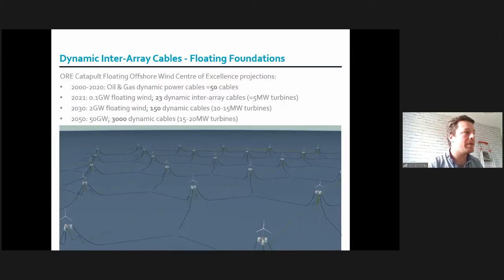So the projections for floating wind that Paul just talked about are very high level. Before floating wind kicked off, we have some quite good experience from oil and gas. So about 20, 30 years of experience on medium voltage and high voltage power cables or umbilicals. And it's maybe about 50 of those cables that we can learn from as an industry and refine those designs. And then in the last few years, we've had quite a steep ramp up of floating wind, of course, about 100 megawatts to date. And that makes up about 20 something cables, relatively small turbines, 5 megawatts.